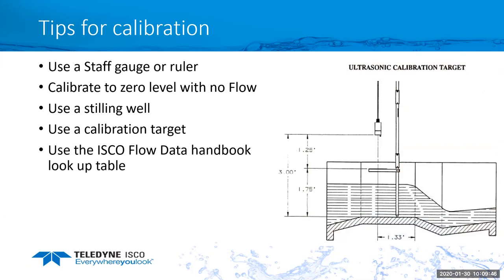And you could also use a calibration target. With ultrasonic sensors, we have a calibration target that you put in the flume, and you set it to a known height. In this case, the example shows 3 feet. So you'd have your target mounted in your flume. The ultrasonic sensor would read the distance and what the level would be at the target. And then you would calibrate your flow meter to, in this example, 3 feet. It's a nice, easy way to do it, and you don't have to worry about the velocity going through, and you know you have a fixed depth that you're calibrating to.